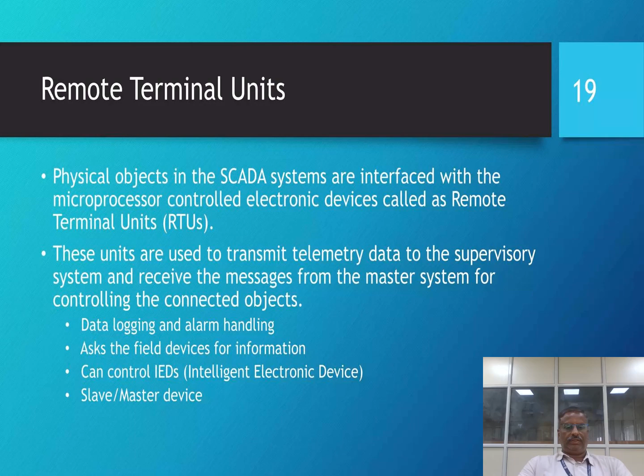So far we discussed the HMI. Next is the remote terminal units. Physical objects in the SCADA systems interface with microprocessor-controlled electronic devices called remote terminal units. These units transmit telemetry data to the SCADA system and receive messages from the master system for controlling the connected objects. They consist of data logging systems, alarm handling systems, asks field devices for information. These remote terminal units can control IEDs, that is intelligent electronic devices, and act as a slave or master device.